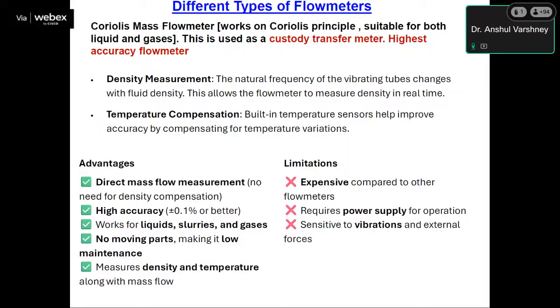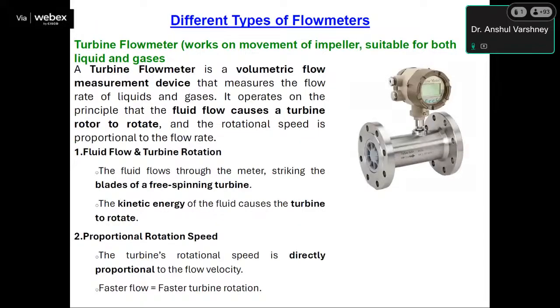There are no moving parts, making it low maintenance. It can measure density and temperature along with mass flow. The limitation is that it is expensive compared to other flow meters. It requires continuous power supply for operation and is sensitive to vibration and external forces. In our CNG, LNG, and PNG dispensers, we are using mass flow meters for measuring the flow rate or totalized volume or mass. Next is the turbine flow meter.